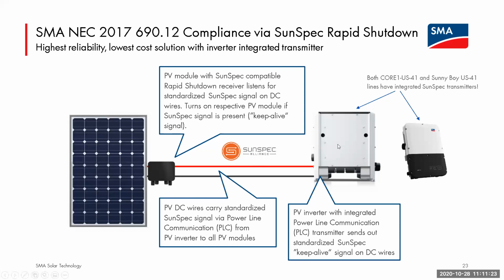When you install the inverter and the SunSpec rapid shutdown device, do you need extra communication boxes or communication wiring to have the inverter talk to these devices to have them shut down? No, we eliminated that by installing in all of our inverters now an integrated SunSpec transmitter. For ground mounts, you just leave it off. For roof mounts, you turn it on through the installation assistant, and it now talks to those rapid shutdown devices behind each module to give you code compliance.